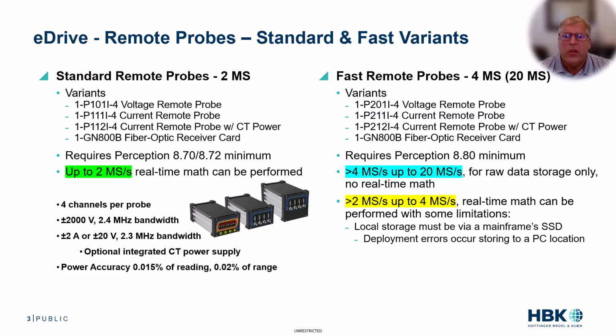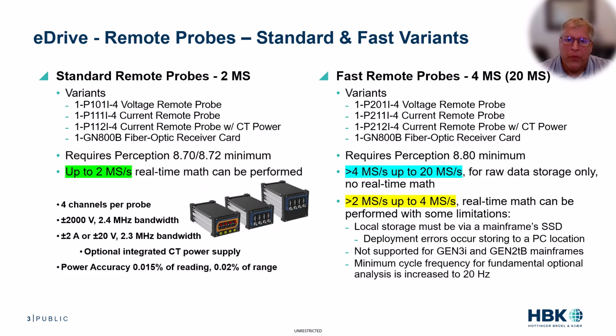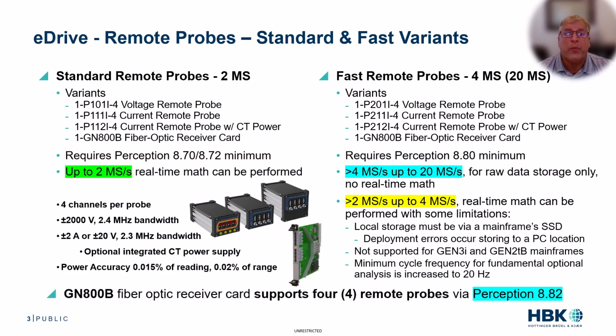For example, you need to use local storage via the mainframe's optional solid-state drive, otherwise you'll see deployment errors occur when storing to a PC location. Now, this ability is not supported on Gen 3i and Gen2tB mainframes, and the minimum cycle frequency for fundamental optional analysis is increased to 20 Hz. And finally, for both variants, a GN800B fiber optic receiver card placed in the mainframe can be used for 2 remote probes, such as 1 pair of voltage and current, or 2 voltage probes if preferred. However, with Perception version 8.82, you can connect up to 4 remote probes on 1 GN800B.